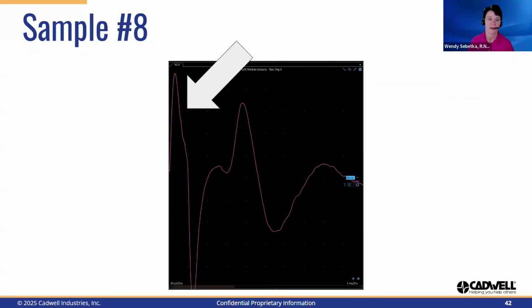Sample number 8 shows an artifact that is consistently occurring prior to the generated response, and at times it obliterates the waveform. A quick observation recognizes this as stimulus artifact, though it is in excess and has the potential of altering the waveform measurements. Shock artifact can be from either physiological or non-physiological sources. Review of this situation's skin condition did not raise a cause for concern, so I was comfortable troubleshooting through the non-physiological sources.